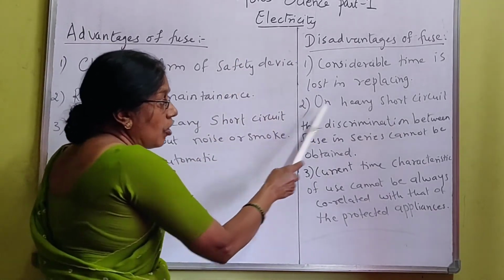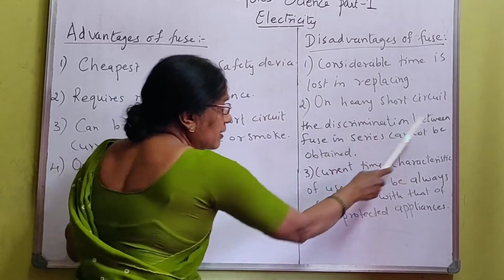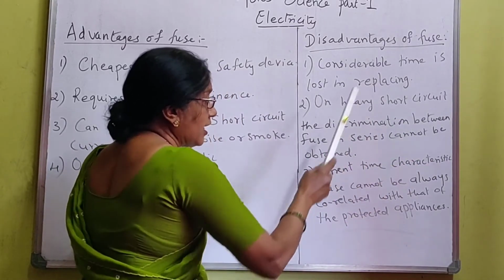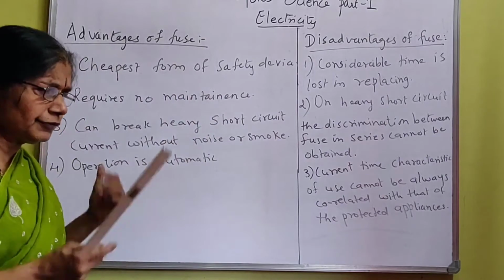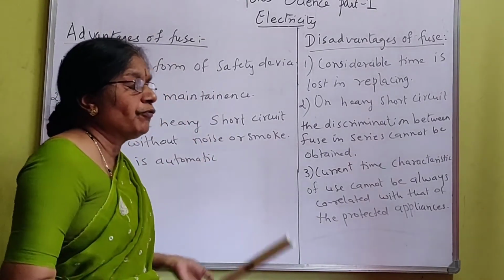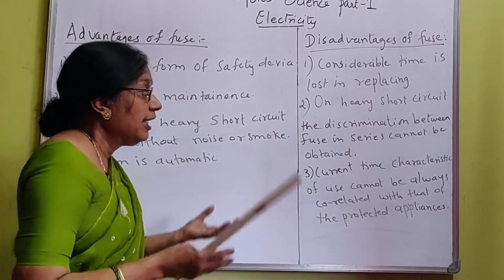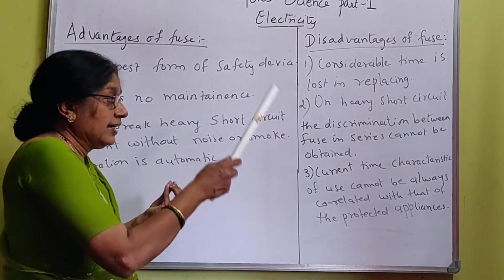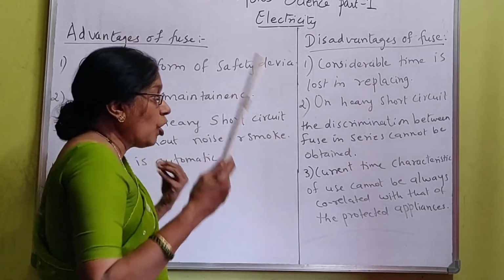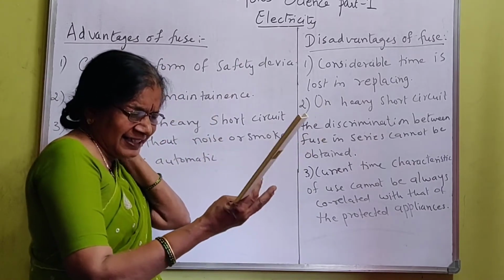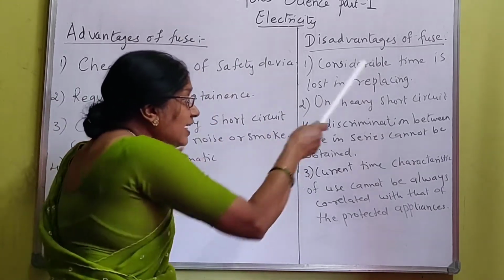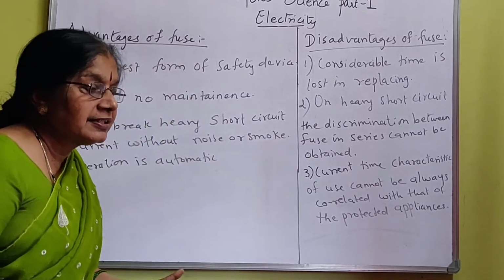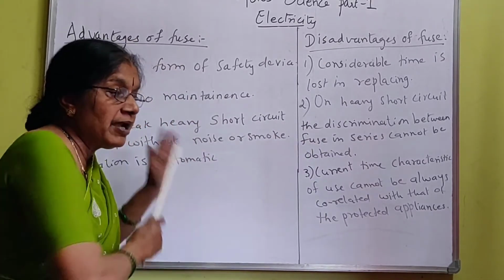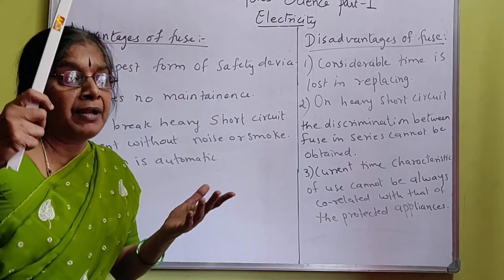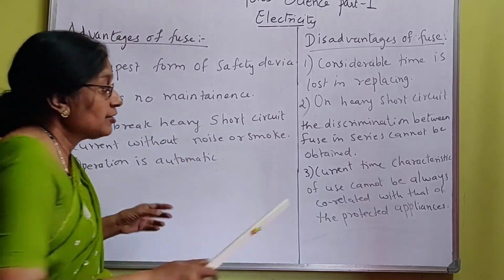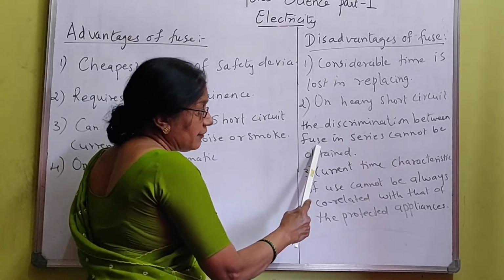The second disadvantage is that on heavy short circuit, the discrimination between fuses in series cannot be obtained. Sometimes, due to a large amount of current entering the circuit, the fuse may not be able to recognize that high current and may not work, allowing it to enter electrical appliances and cause damage.